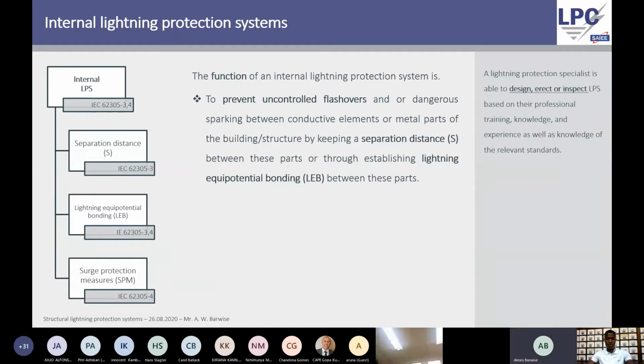The function of an internal lightning protection system is a very simple expression, but quite a complex thing to achieve at times. And so I'm really excited to share this with you, and also Professor Gomez will get into one of the critical parts, the surge protection measures. But in very simple terms, the function of an internal system is to avoid any flashovers, sparking, or arcing.